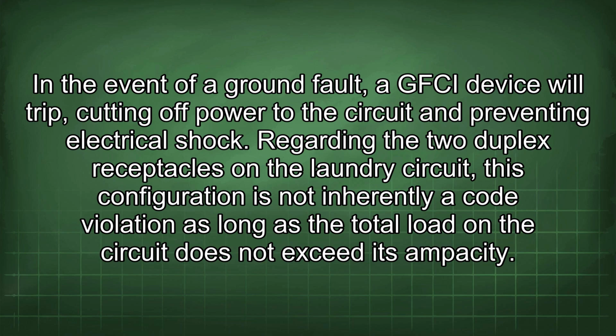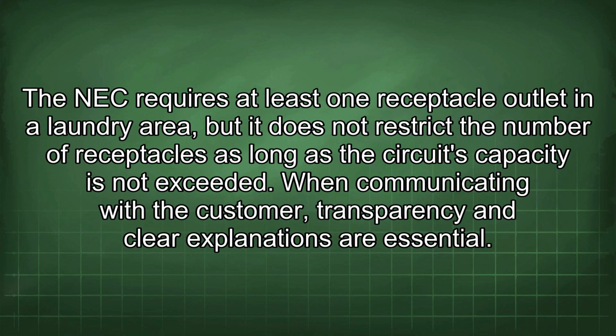In the event of a ground fault, a GFCI device will trip, cutting off power to the circuit and preventing electrical shock. Regarding the two duplex receptacles on the laundry circuit, this configuration is not inherently a code violation as long as the total load in the circuit does not exceed its ampacity. The NEC requires at least one receptacle outlet in a laundry area, but it does not restrict the number of receptacles as long as the circuit's capacity is not exceeded.